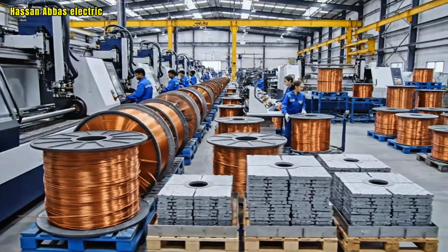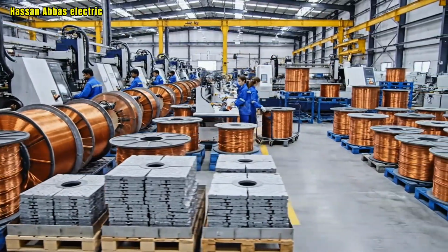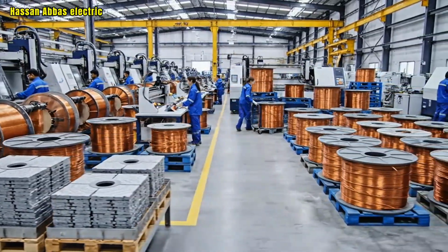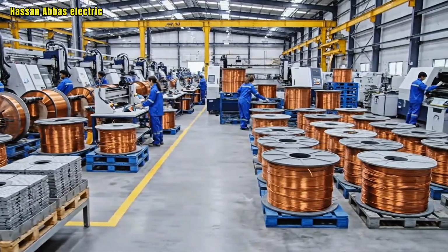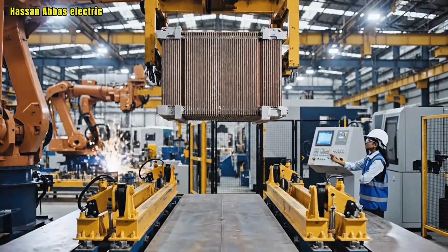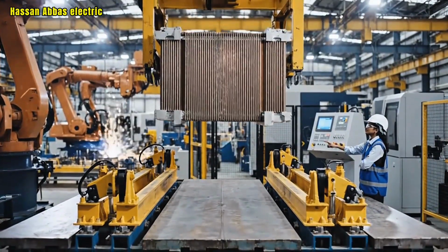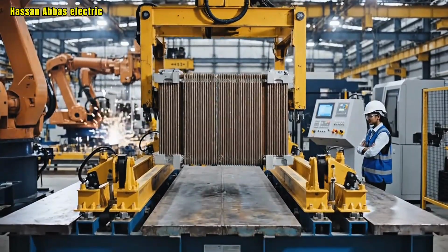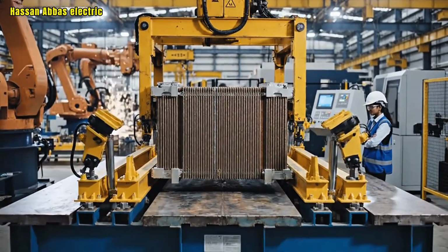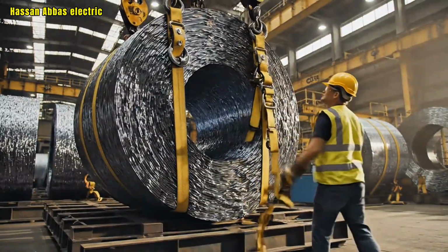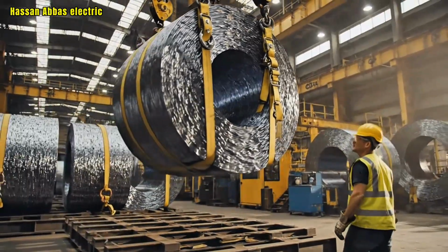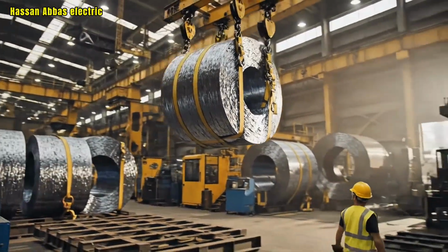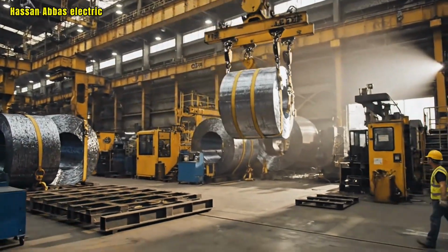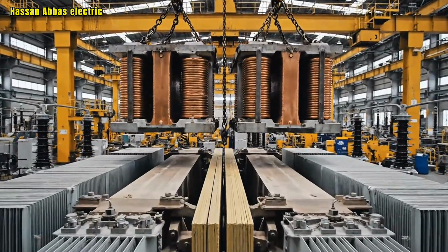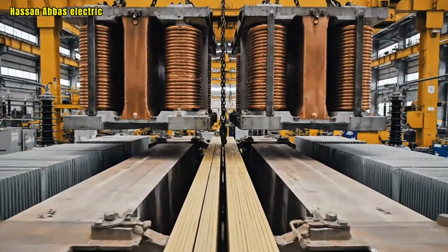The winding section is organized and ready for internal assembly of transformers. The transformer core is positioned for final internal assembly. Finished coils are prepared for safe lifting and placement. The coils are carefully placed onto the transformer core.